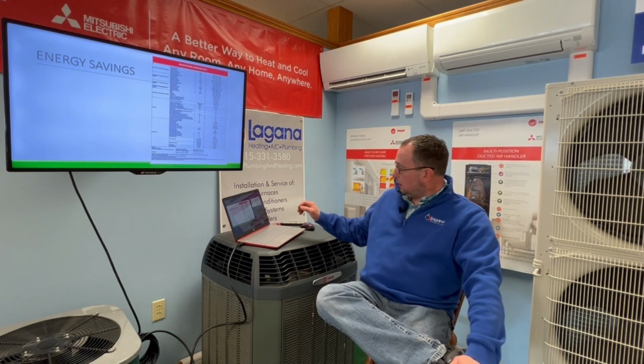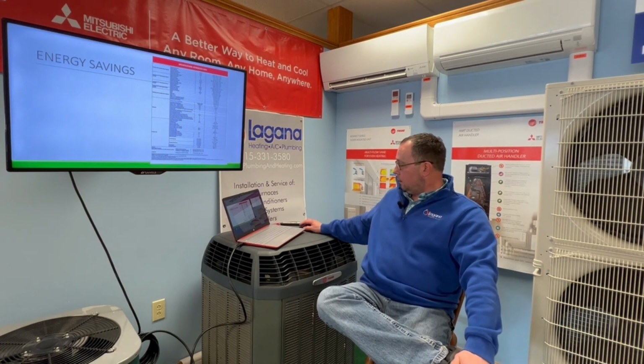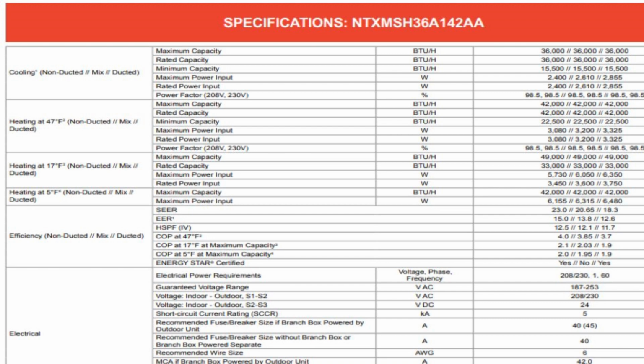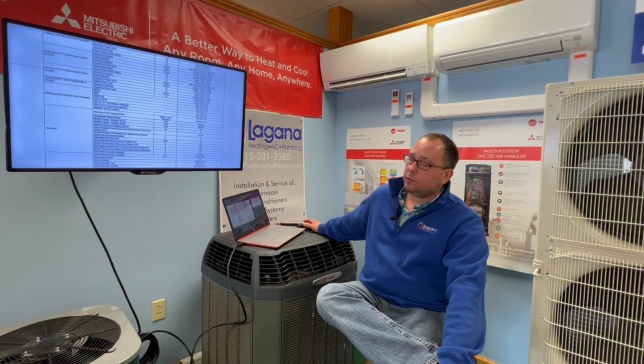It's a multi-zone system. What Mitsubishi will provide for us is different specifications at different outdoor temperatures, which we can see. I'll zoom in on this. If we look at heating at 17 degrees, we see that we have a maximum capacity of roughly 49,000 BTUs. We also have a maximum power input. In this case, to generate those BTUs would take 5,730 watts. So we'll use those numbers for our model.